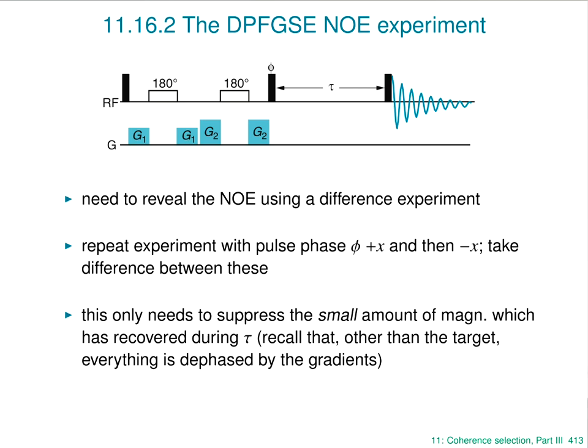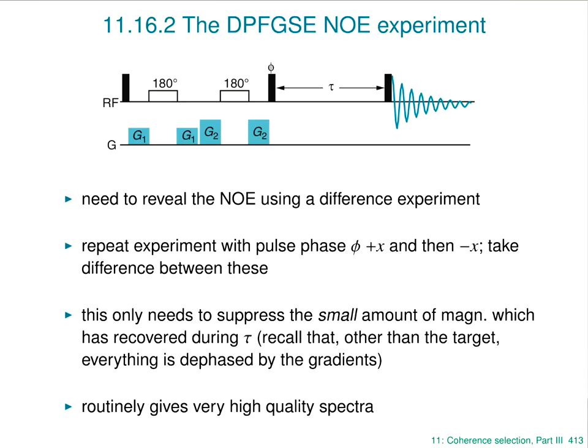The really important point is that because all the other signal is dephased, the difference you're calculating is between two rather small things. One of the problems with the NOE experiment has been that in the control experiment most peaks are full intensity, and in the NOE experiment most peaks are full intensity. Taking the difference between two large things puts a lot of stress on spectrometer stability. With this method, because almost all magnetization is dephased, you're creating a difference between two much smaller quantities. This routinely gives extremely high quality spectra, and this experiment has really revolutionized the quality you can get from 1D NOE spectra.